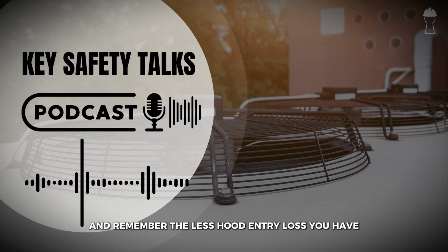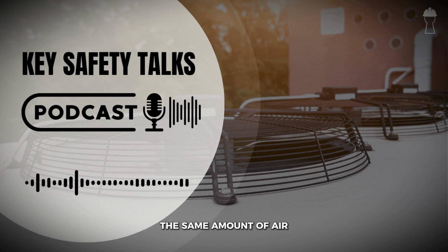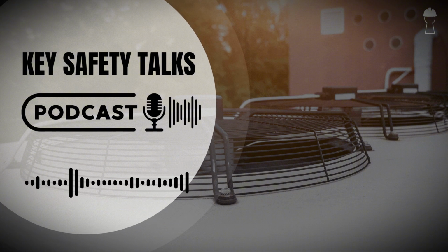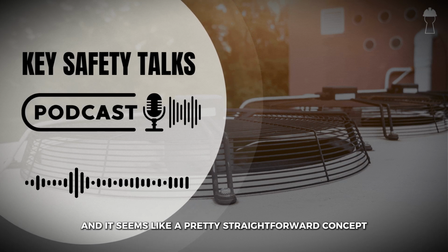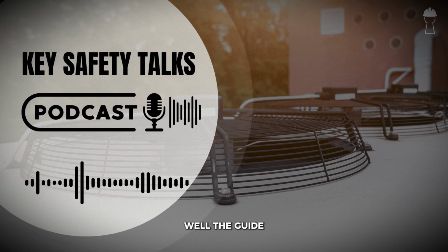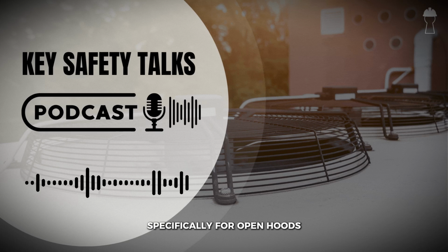And remember, the less hood entry loss you have means the fan doesn't have to work as hard to move the same amount of air, which saves energy and ultimately saves money, too. Now, let's get back to capture velocity. We talked about that earlier, and it seems like a pretty straightforward concept, but how is it actually calculated? Well, the guide gives us a helpful equation for calculating capture velocity, specifically for open hoods.